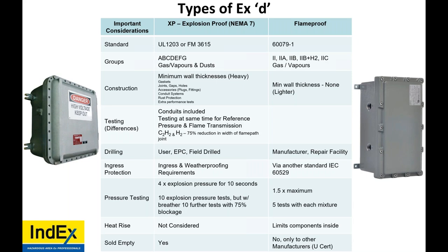Another one that Thornton from Stahl actually gave good input on is that explosion proof is only for division one. EXD, flame proof, is only for zone one. So when people say EXD, this confusion is going to continue because EXD is used for calling explosion proof and flame proof. And some trainers around the world continue to spread this inaccuracy.